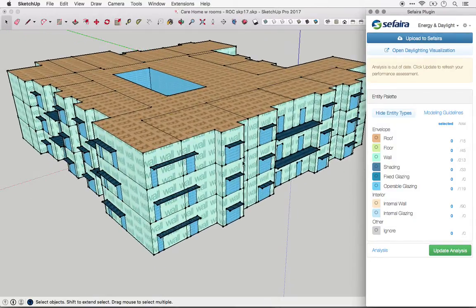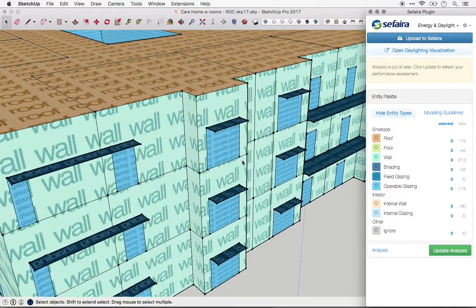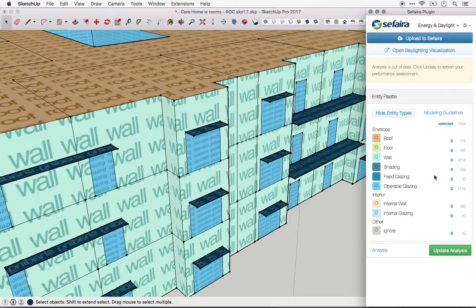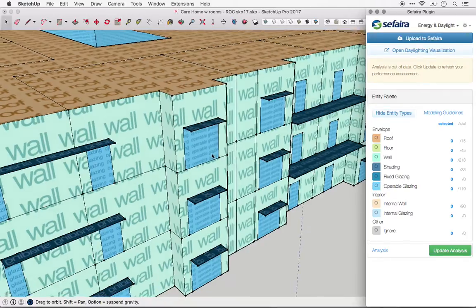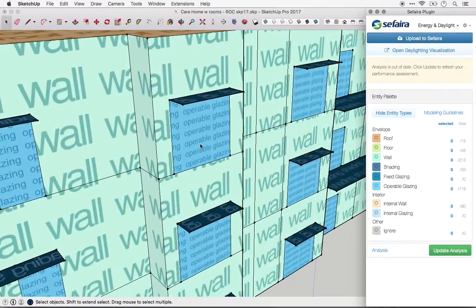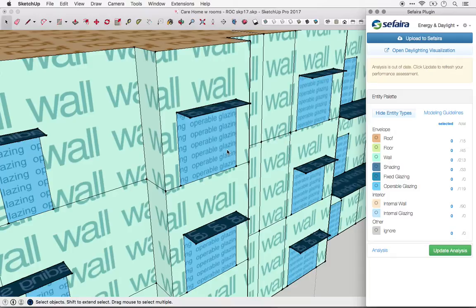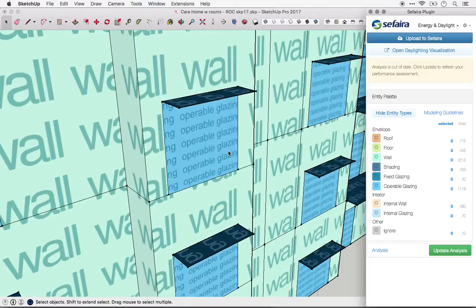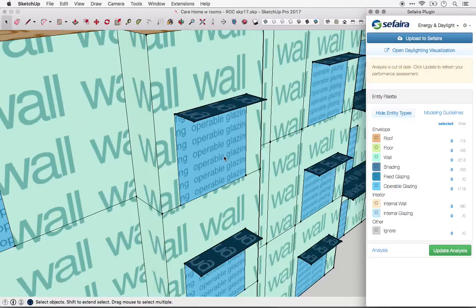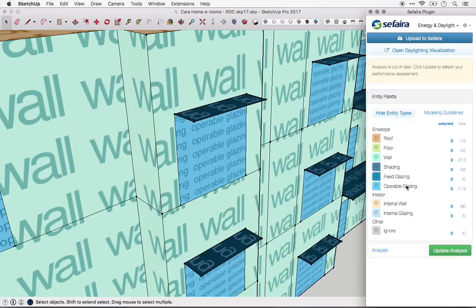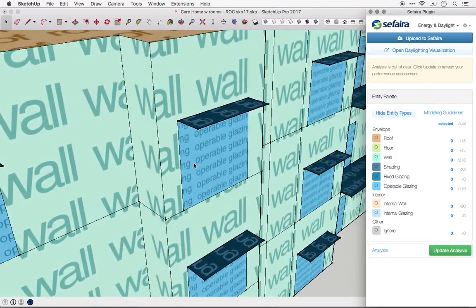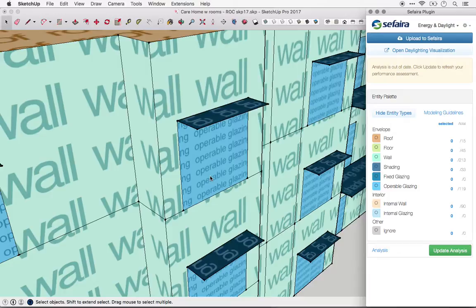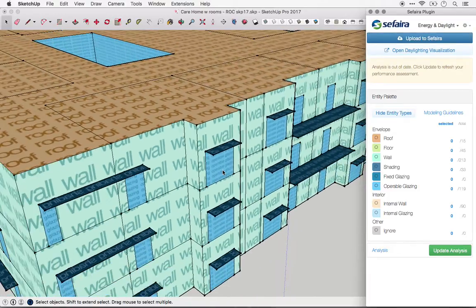Next is glazing. You'll see two types of glazing in the entity palette, fixed and operable. These are both glazing that has thermal transfer between inside and outside, so should be used as part of the thermal envelope. The only difference is how they're considered for natural ventilation calculations, which can be done in the web application. Operable glazing can be opened and fixed cannot. By default, all glazing is assigned as operable glazing.